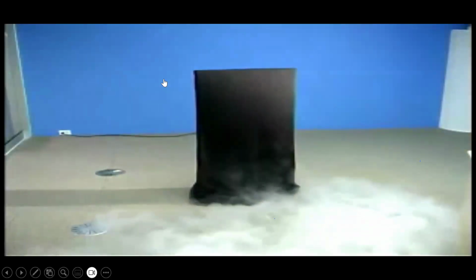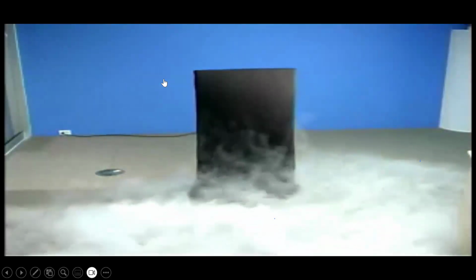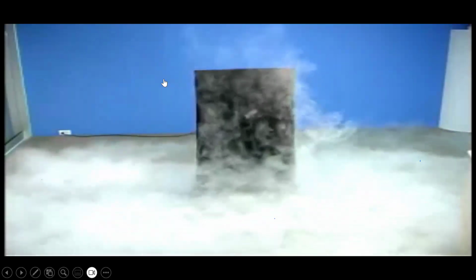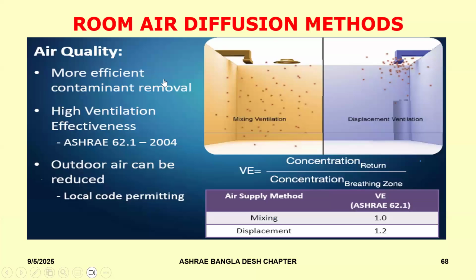and then you are breathing that air, right? So if you have a room like this with two human beings, each of you is getting the same good fresh quality of air, unlike the air which is mixed in the room. If the air is mixed in the room, each person's pollutant can get mixed, and you can be breathing and sharing that air. So that is the basic difference that you will see, as is illustrated over here. The displacement has a more efficient contaminant removal, and therefore it gives you ventilation effectiveness as 1.2. But like I said, how well you design this will also decide whether it is 1.2 or 1.4. We have seen systems which provide effectiveness as high as 1.4, which means you require roughly around 33% less outdoor air than you would in case of a fully mixed system.